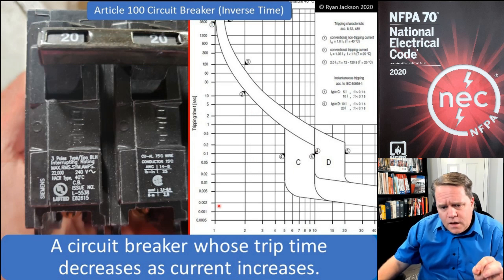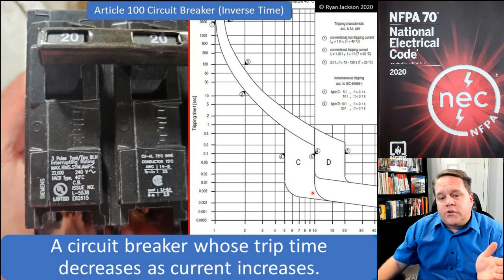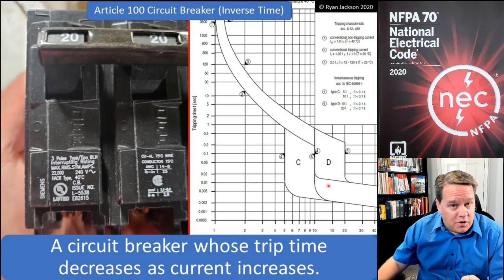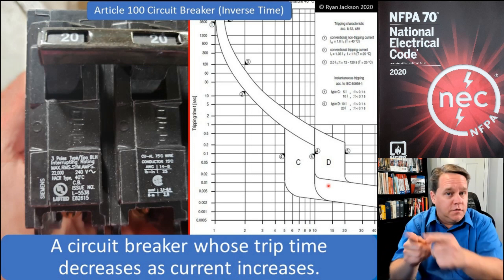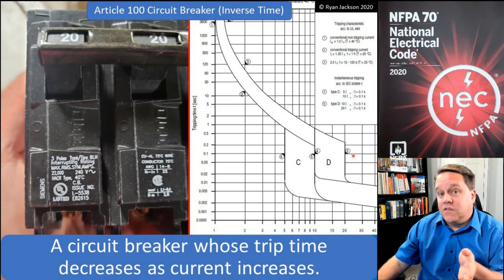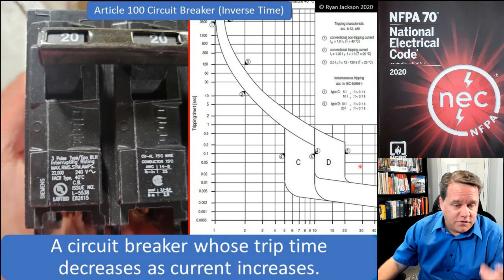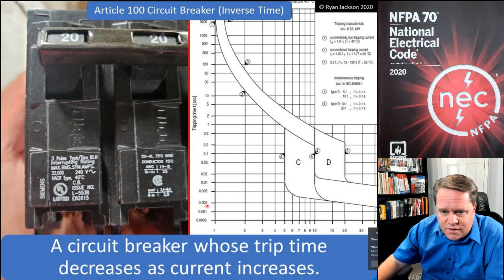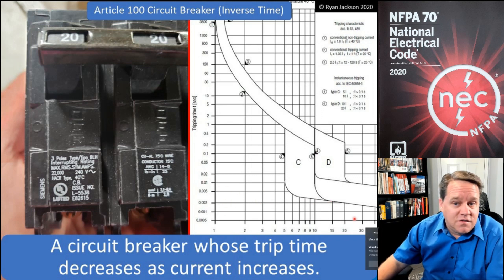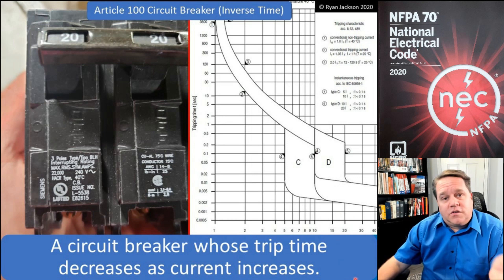If I show this breaker 10 times its rating — 200 amps — we're now in the magnetic part of the circuit breaker, no longer on the bimetal thermal overload part. That's where we start measuring things not in seconds but in cycles or fractions of a cycle. At 200 amps on a 20-amp breaker, it'll trip at around 0.002 seconds. So you get the idea: trip time decreases as current increases — that's our inverse time circuit breaker.